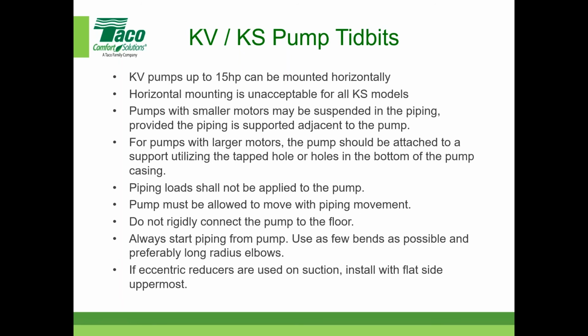If eccentric reducers are used on suction, put the flat side on the uppermost, and that way you still get nice smooth flow into the pump. And then very important, the last tidbit on this page: don't cover the motor with any insulation. Don't cover the motor with any insulation. A lot of this stuff probably makes sense or is easy to understand, but nonetheless, it's good to have it there in that regard.